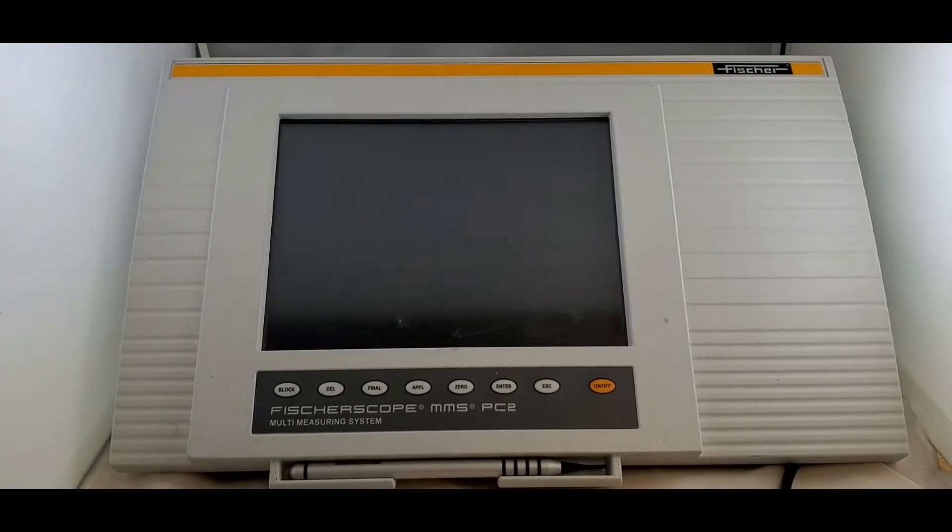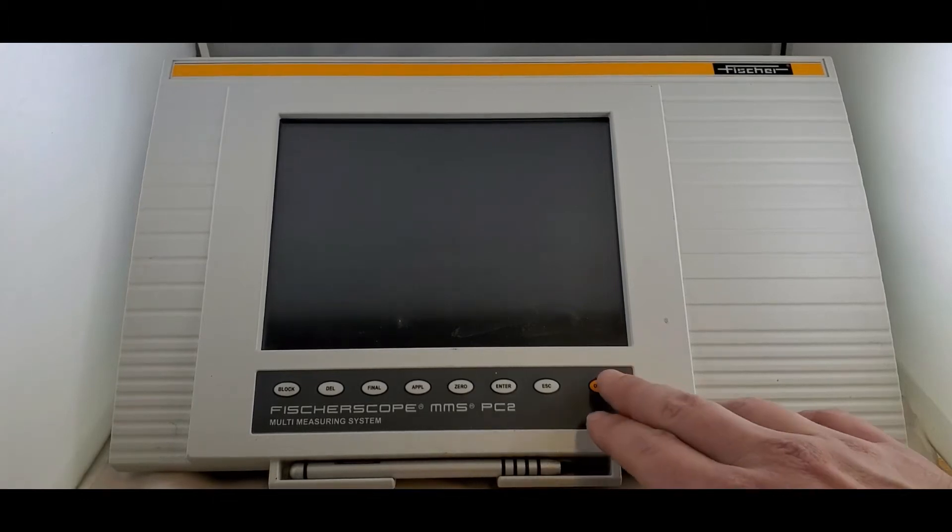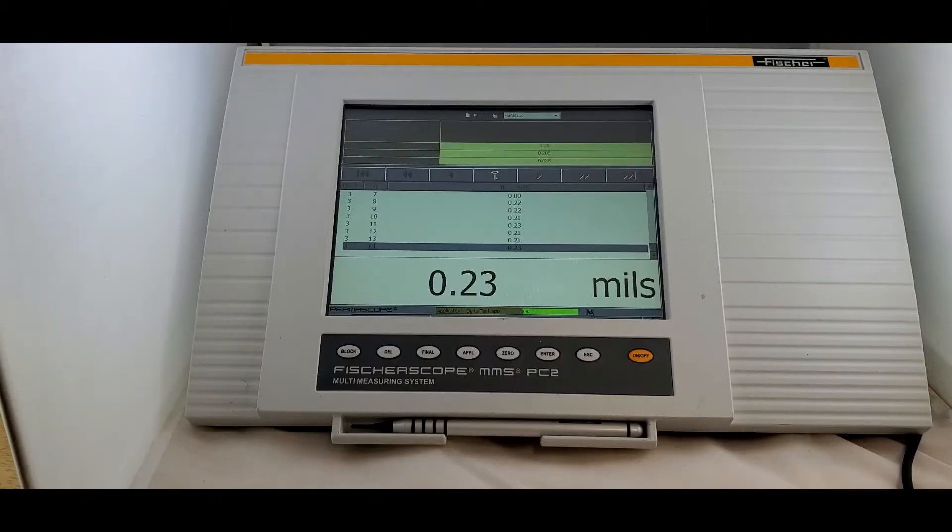Les from Delta here with the Fischer MMSPC2. Let's talk about how to calibrate this. So for calibration, we're going to start from the application that you're using. If you're running multiple applications, each one needs to be calibrated individually.